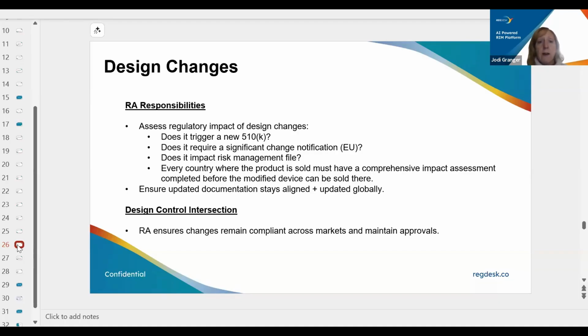Will it trigger a new 510(k)? Will it require a new submission as a significant change to a notified body? Do you have an impact to your risk management file? Do those risk management files need to be updated? Every single country where the product is sold must have a comprehensive impact assessment completed before that modified device can be sold there.